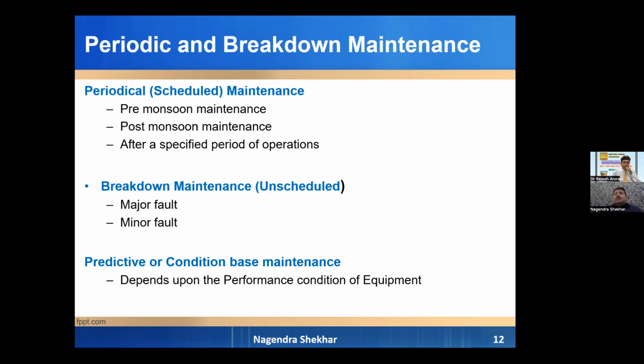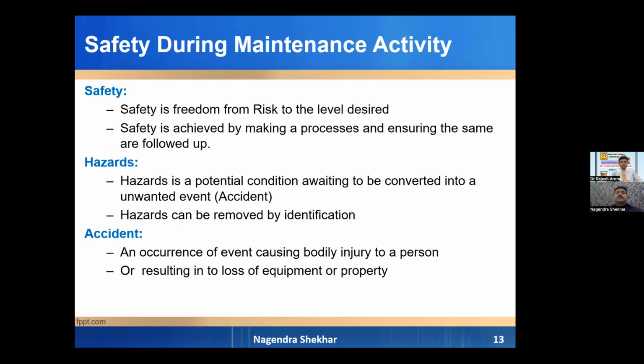Breakdown maintenance results from major or minor faults. Major faults are broken conductors, and minor faults are those which can be restored, or broken overhead lines, equipment failure like a transformer, major fires. And condition-based maintenance, I have already told you, depends upon the condition of a particular equipment or line. Suppose there is a high sag in an overhead line, or a pole has leaned down. So these are the conditions, and you can take maintenance activity proactively.